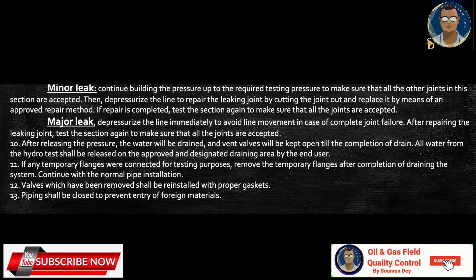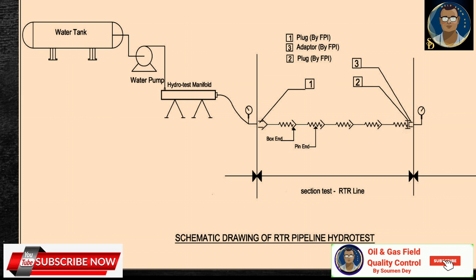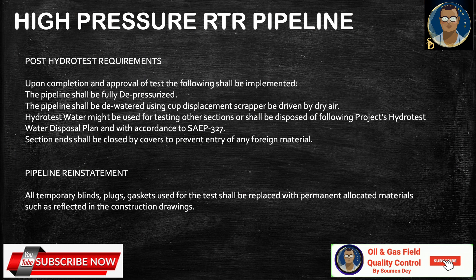Valves which have been removed shall be reinstalled with proper gaskets, and piping shall be closed to prevent entry of foreign materials. The setup schematic for the RTR pipeline hydrotest shows a water tank feeding through a water pump to the hydrotest manifold, from which controlled flow enters the pipeline system. Post-hydrotest requirements include: fully depressurizing the pipeline, dewatering using cup displacement scraper driven by dry air, disposing of hydrostatic water per the project hydrotest water disposal plan and client standard, closing section ends with covers, and replacing all temporary blinds, plugs, and gaskets with permanent materials as reflected in the construction drawings.